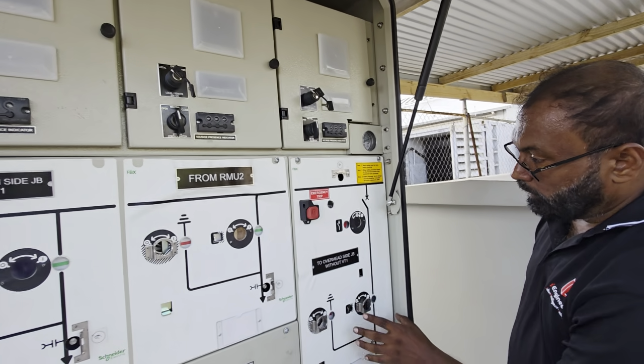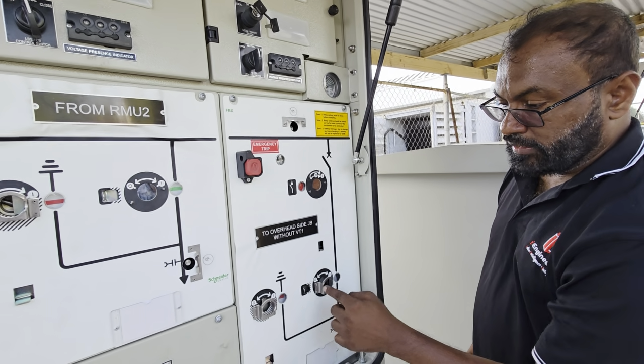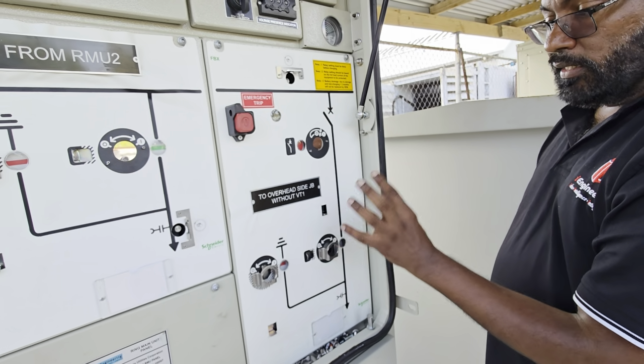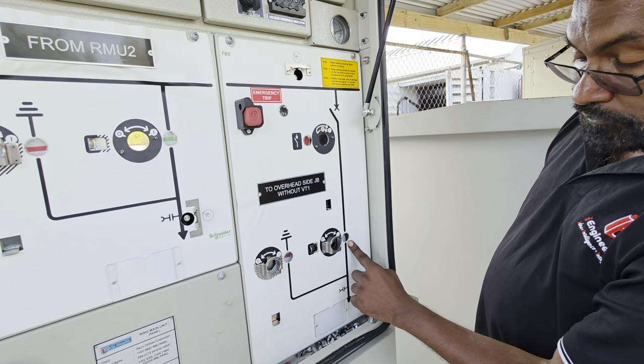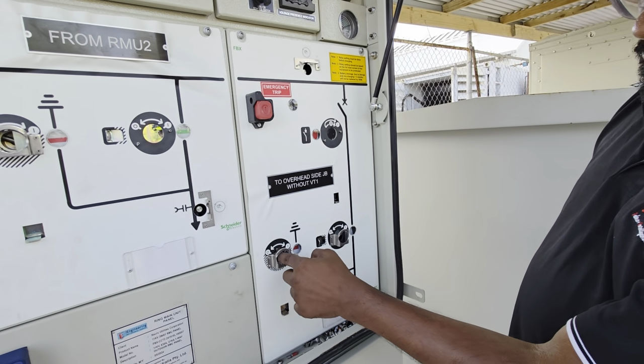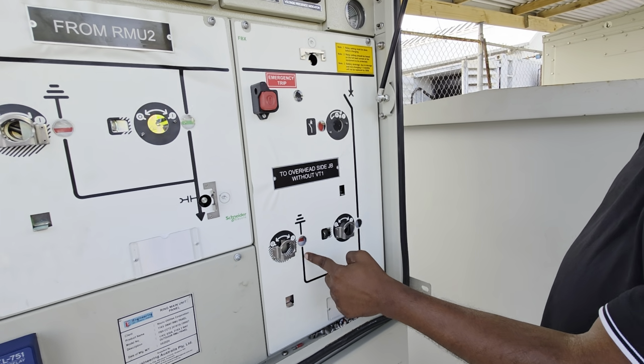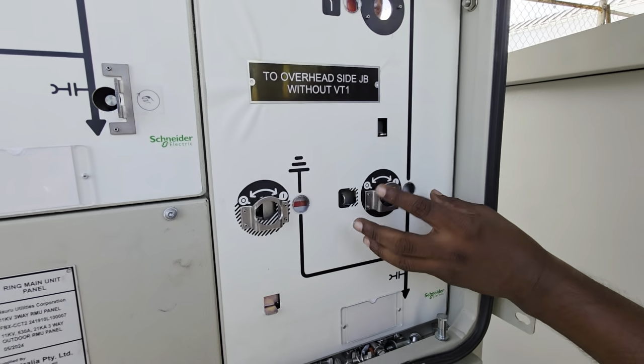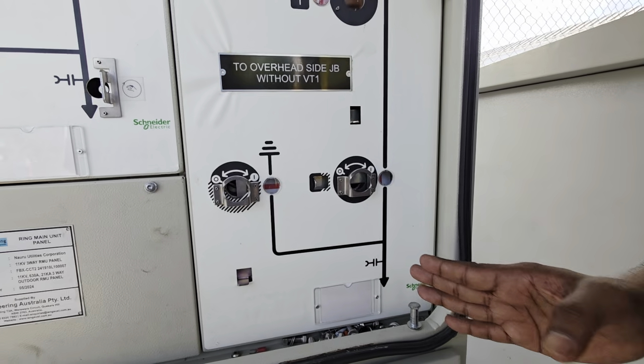Now over here, there is no earth here, but there is an earth showing on this part. Again, if the disconnector is on like that, you cannot put it to earth, and if it is earthed, you cannot close your disconnector. So that's how it works.